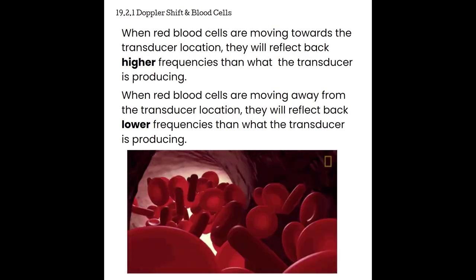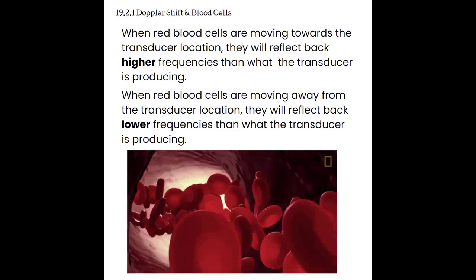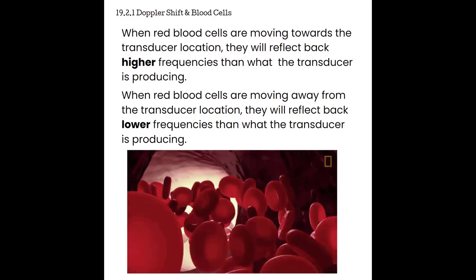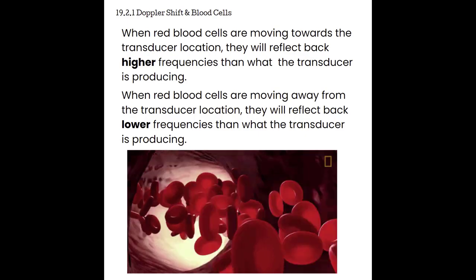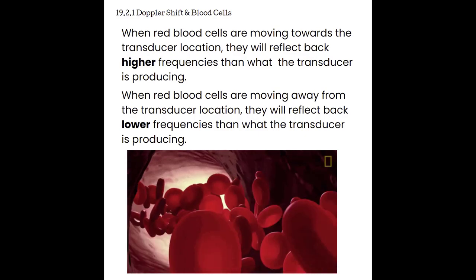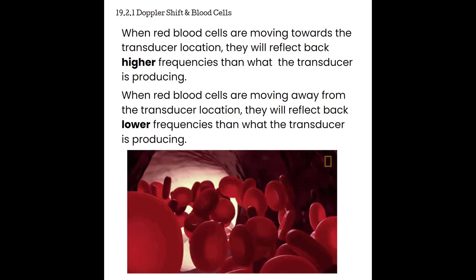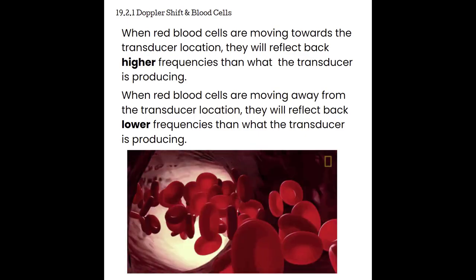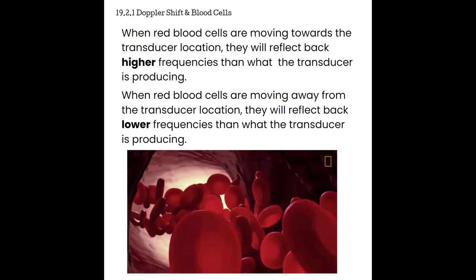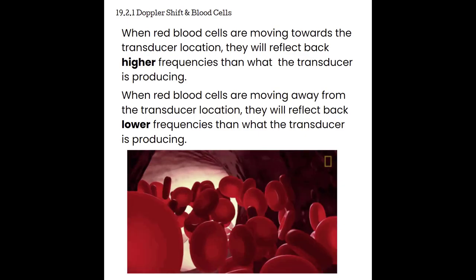A Doppler shift can be detected by the machine when it evaluates the frequency of echoes returning from moving reflectors — which are our red blood cells. When red blood cells move towards the transducer, they reflect back higher frequencies than what the transducer produces. When they move away from the transducer, they reflect back lower frequencies. Red blood cells moving towards the transducer produce a positive shift; red blood cells moving away produce a negative Doppler shift.